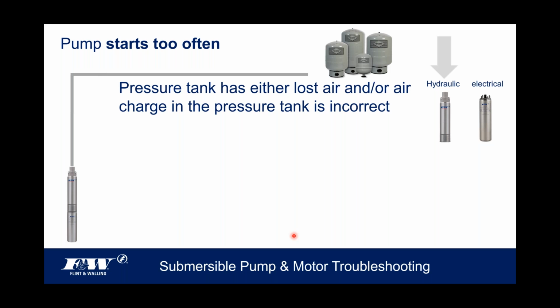The pressure tanks. Now, back in the day, these tanks were all galvanized steel, and they didn't have an air cell inside like a bladder or a bag. These were galvanized steel tanks, and the installer would go out there with an air compressor and pump air in the thing just to give some air charge to that tank. The problem with galvanized steel tanks is that over time, the water would absorb that air, and it would eventually lose the air charge. So if a pressure tank has either lost air or the air charge in the pressure tank is incorrect, this is going to cause the pump to cycle.